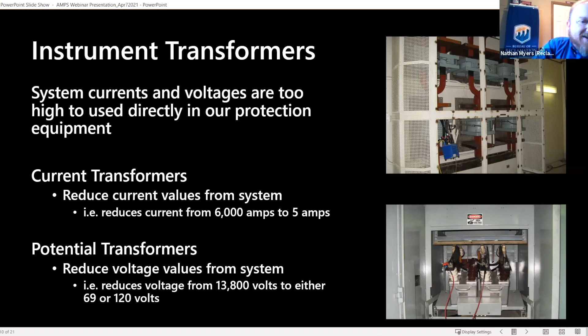Our potential transformers reduce the voltage values from the system. So for example, in many of our instances, we'll be operating at 13,800 volts, and it'll reduce it down to either 69 or 120 volts, depending on how the protection system is set up.